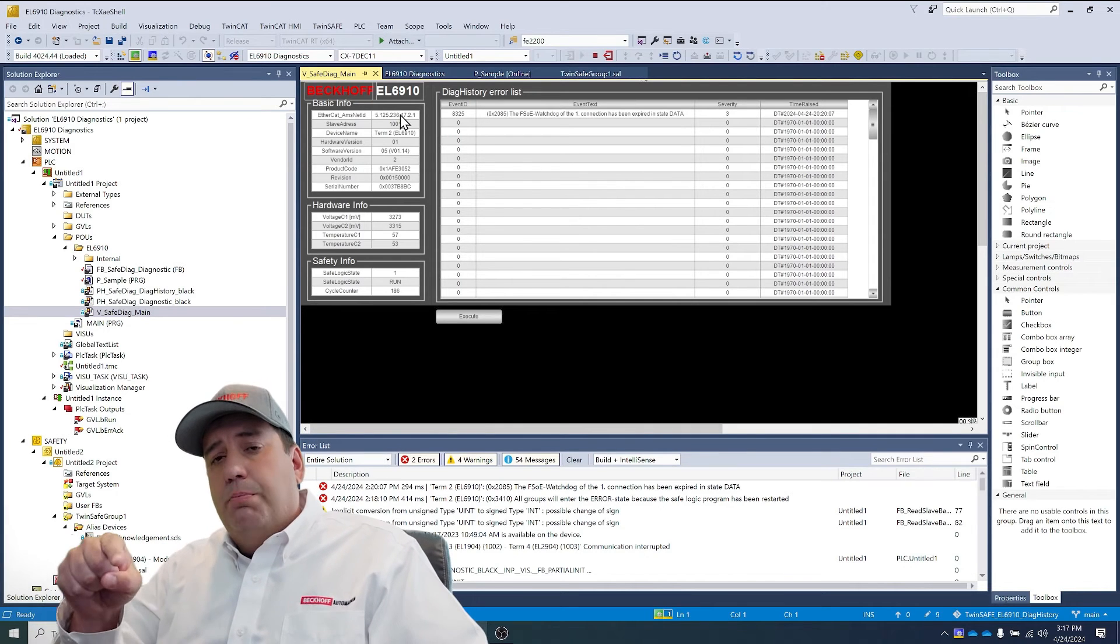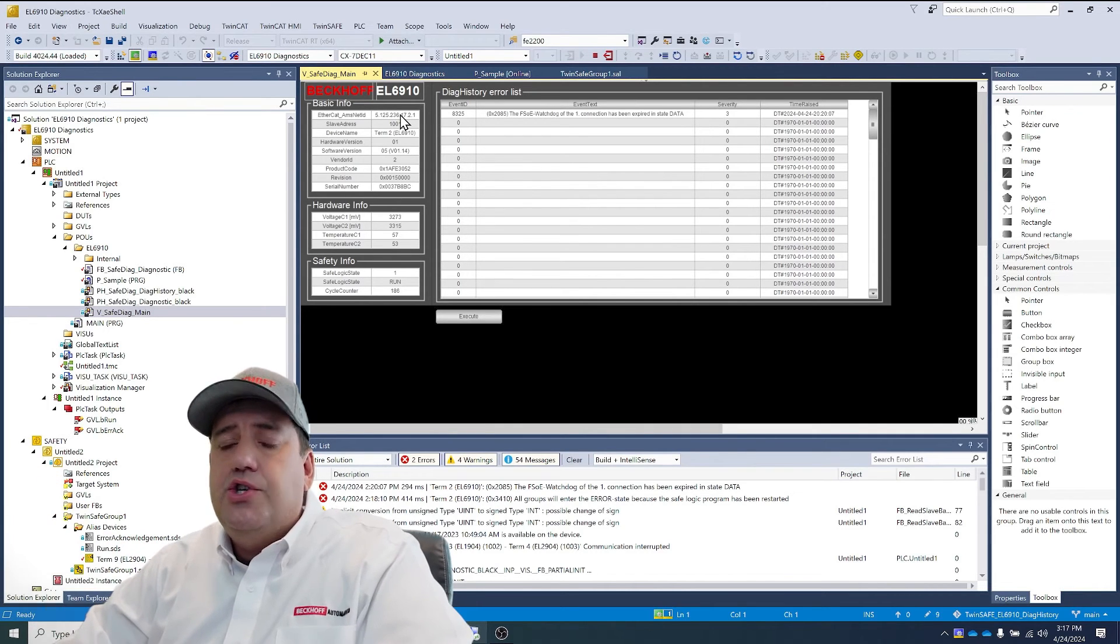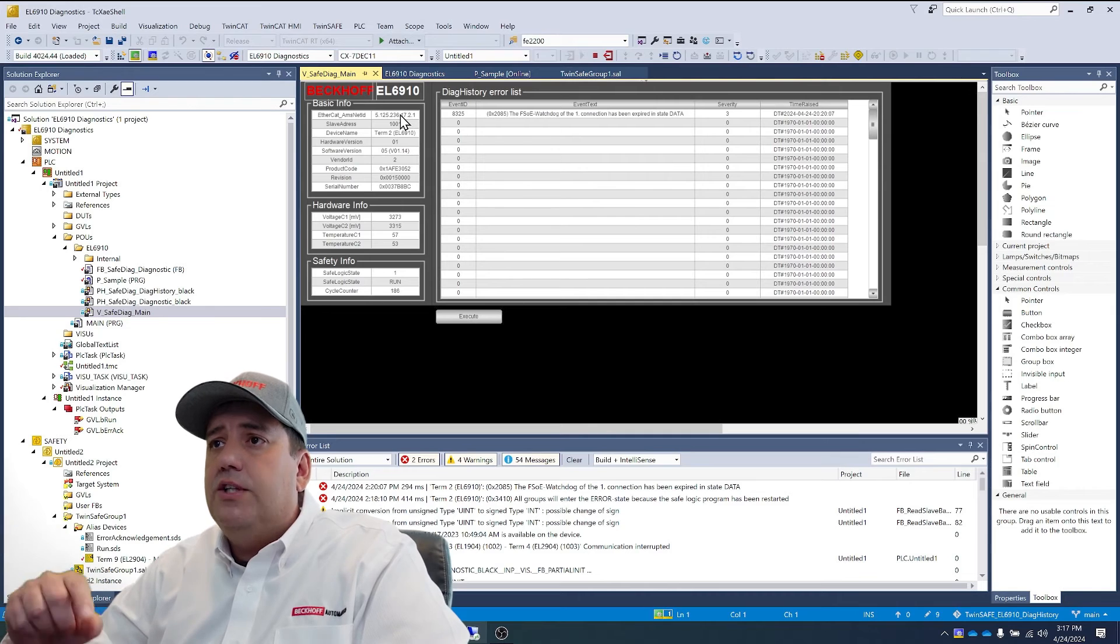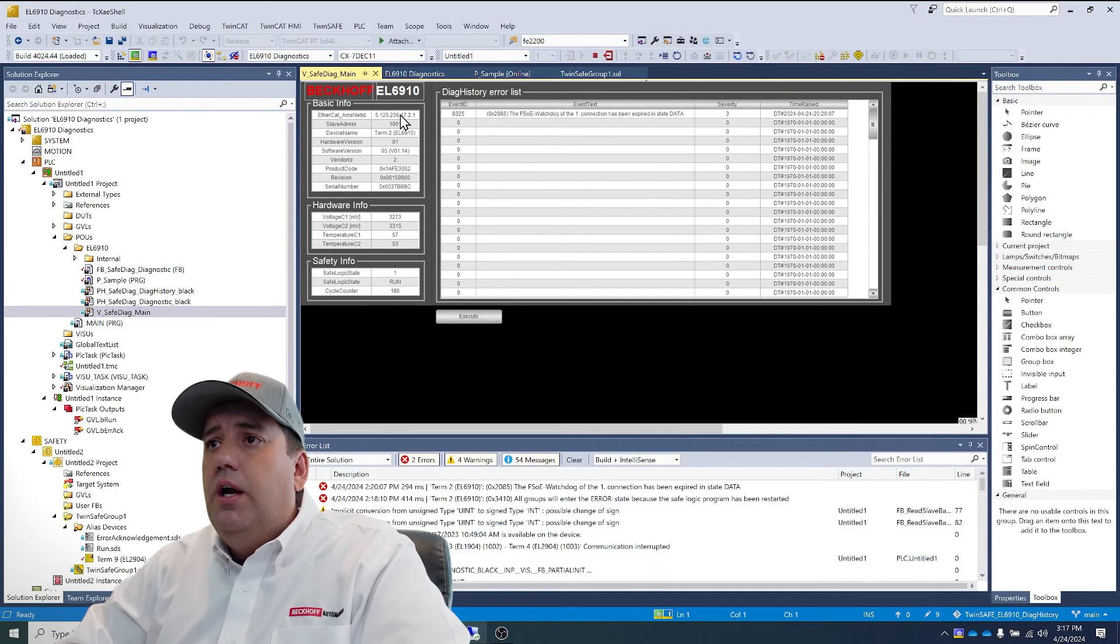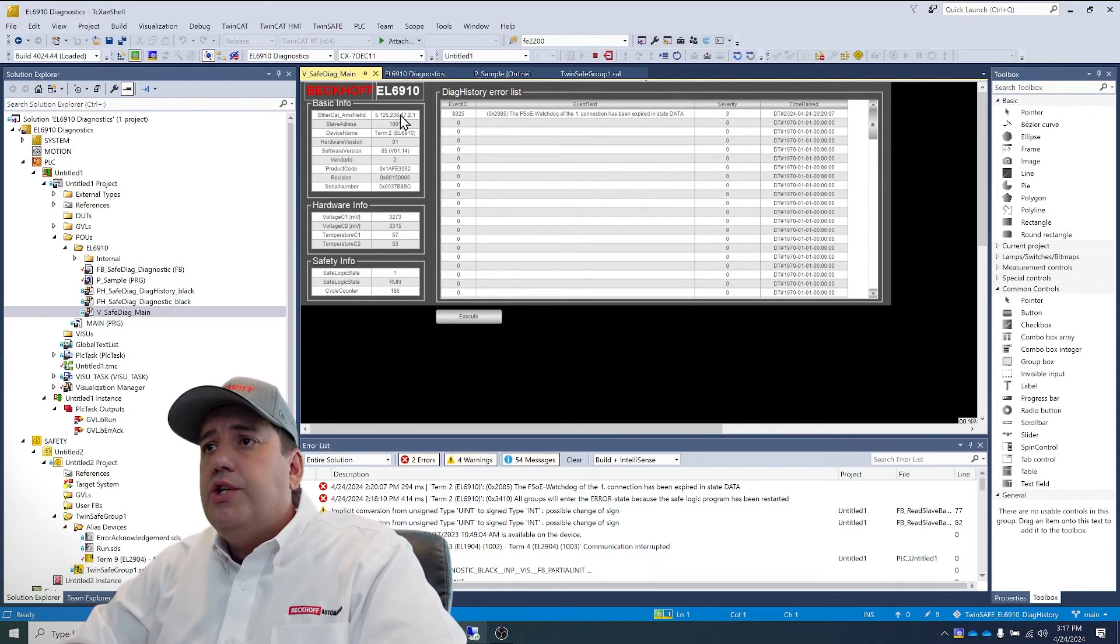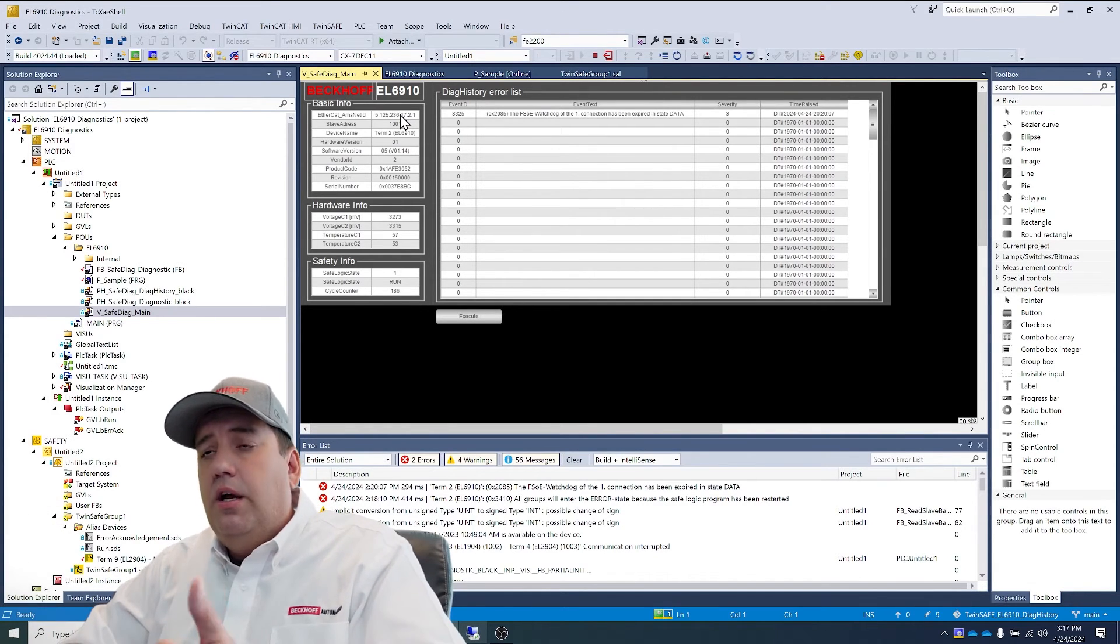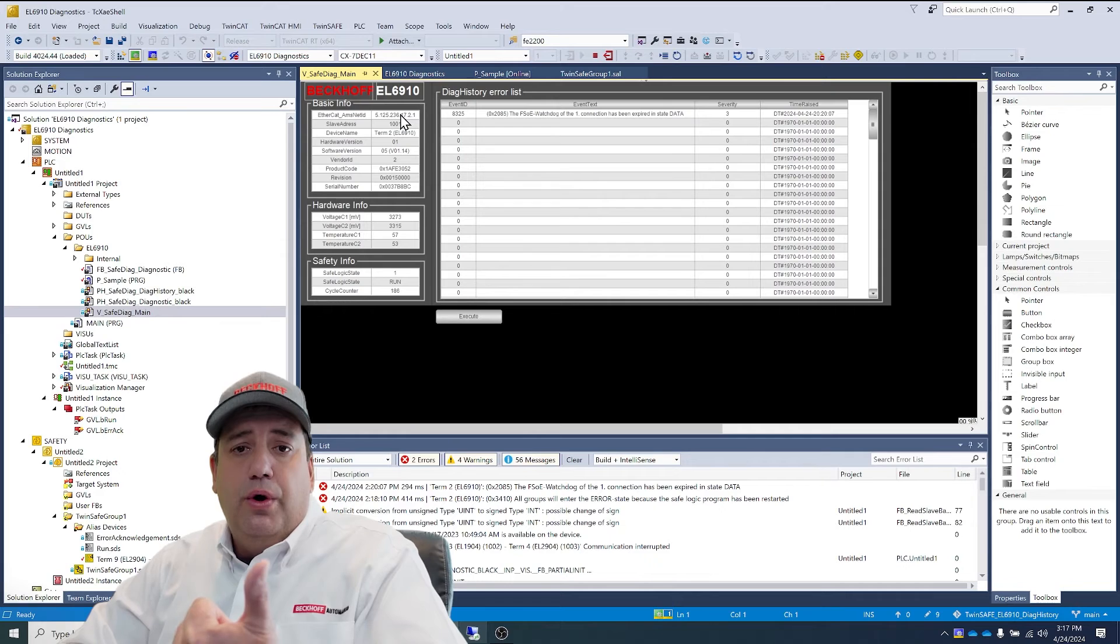But most importantly, we're seeing the diagnostic history error list. So we see that the FSOE watchdog of the one connection has been expired. That's the EL2904.